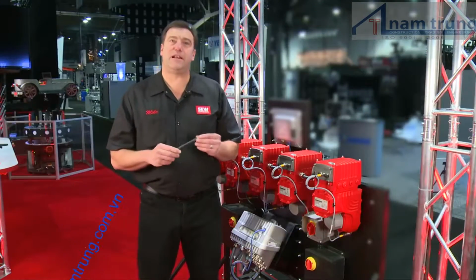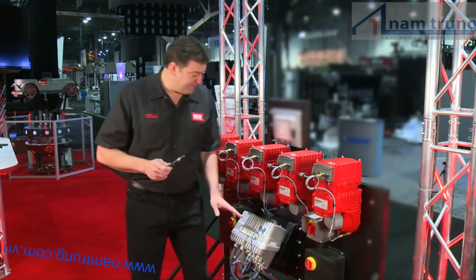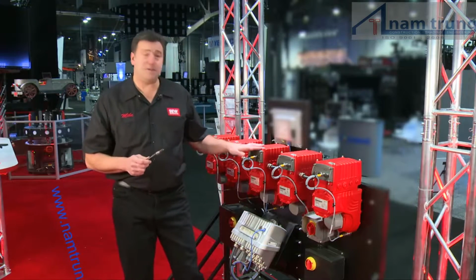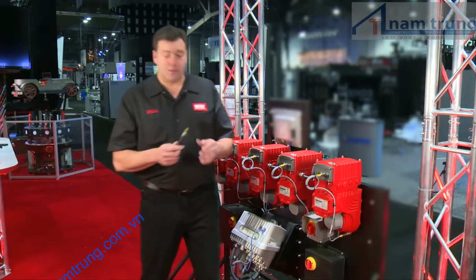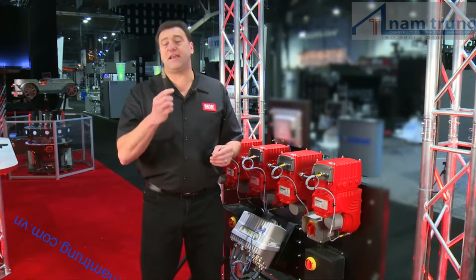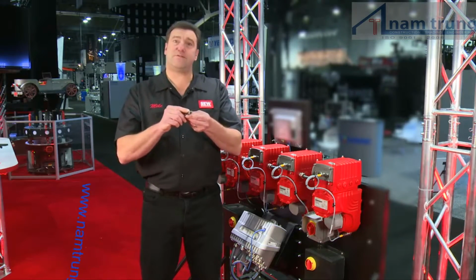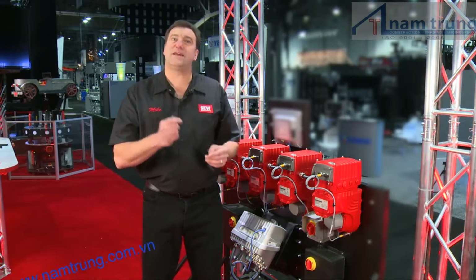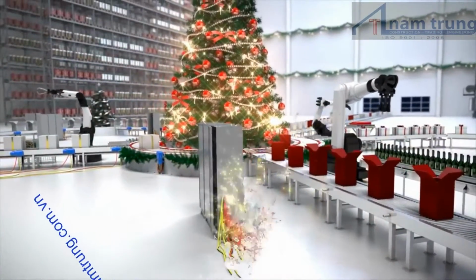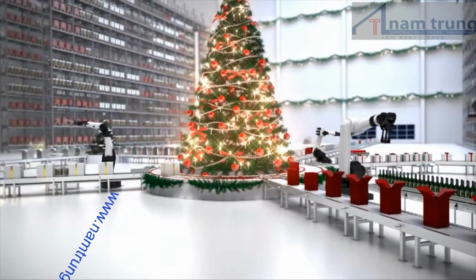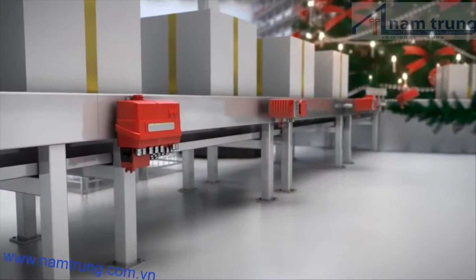Let's talk a little bit about our SNI network. We use the FDC controller to control up to 10 MOVIGEARs on this network. The way this network works is we take our power cable and also transfer our control signals over the same power cable. This eliminates the cost of a large installation because we're only running one single cable to each MOVIGEAR.